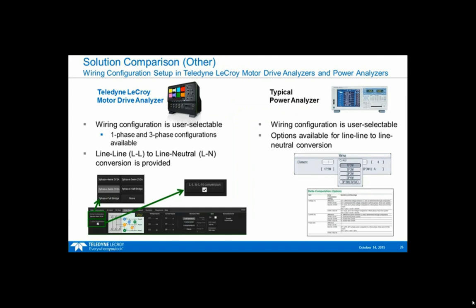A couple other things that are different about these two products. Basically, both a motor drive analyzer and a power analyzer have different ways to select the wiring configuration. You can probe line to line and do a line to neutral conversion. Both these tools support these things. Basically, they're pretty much the same in that regard. This is a typical power analyzer, of course. That's a Yokogawa, probably the better known one of all the ones that are manufactured.